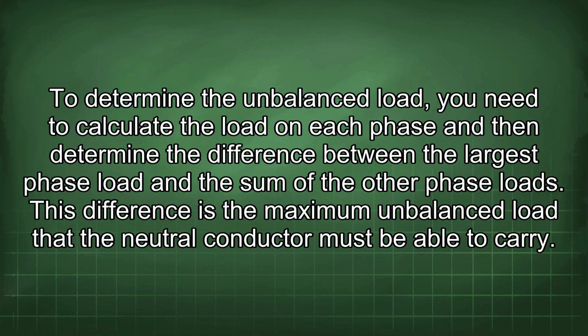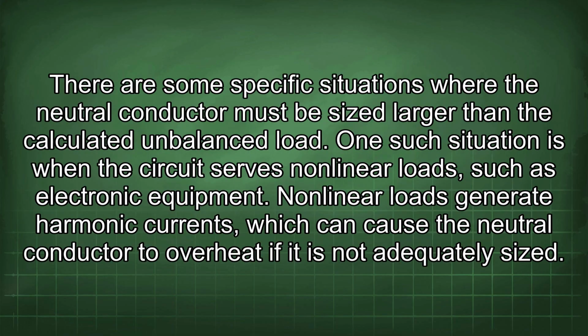To determine the unbalanced load, you need to calculate the load on each phase and then determine the difference between the largest phase load and the sum of the other phase loads. This difference is the maximum unbalanced load that the neutral conductor must be able to carry. There are some specific situations where the neutral conductor must be sized larger than the calculated unbalanced load. One such situation is when the circuit serves nonlinear loads, such as electronic equipment.